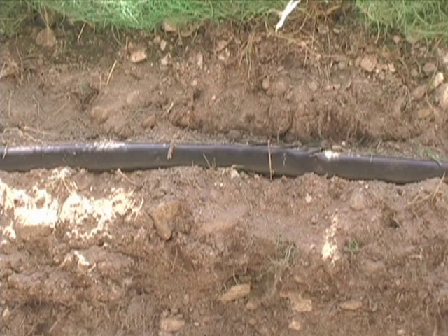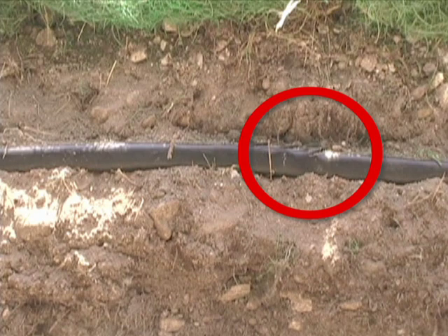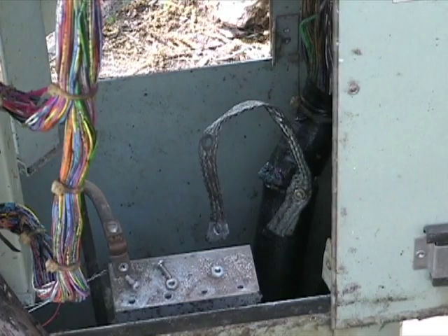will find earth return faults. An earth return fault is one in which an insulated conductor is physically making contact to the dirt due to some damage that has occurred to the insulation of that conductor. When fault locating, the first step is to isolate both ends of the faulted section of the cable. There should be no physical connection on either end of the cable.